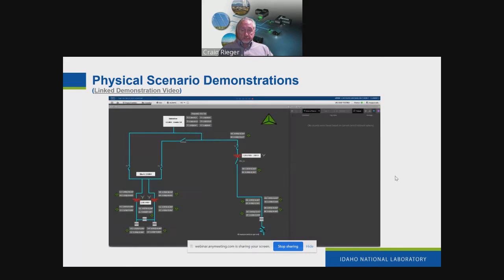We can do a second attack at a different point in the system. Again, we can detect this attack with an incorrect measurement. We see an indication on the triad, and we also have an alert message that's generated. This approach can work with larger numbers of corrupted measurements. In cases where there is insufficient visibility to correct for these at the substation level because of the number of corrupted measurements, the Tier 2 estimator is also able to detect those anomalies.